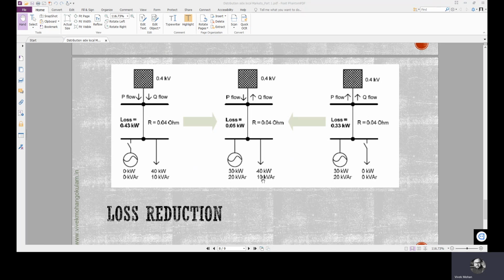Now here we are going to connect the local generator, and 30 kilowatts of active power is generated locally, and 20 kVAR of local reactive power is generated from here. So out of this 40 kilowatts, 30 is fed locally and 10 will come from the upstream grid. Of course, some losses are there, but in general, the direction is towards the local node. So Q flow has reversed.